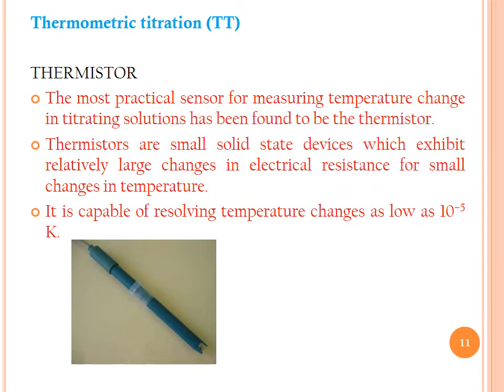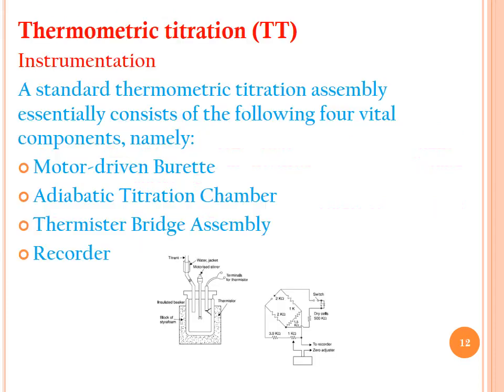The most practical sensor for measuring temperature change in a titrating solution is the thermistor. Thermistors are small solid-state devices that exhibit relatively large changes in electrical resistance for small changes in temperature. They are capable of detecting temperature changes as low as 10⁻⁵ K, sensing very minute changes occurring between the reaction of titrant and titrand. The standard TT assembly consists of four vital components: a motor-driven burette, an adiabatic titration chamber, a thermistor bridge assembly, and a recorder.